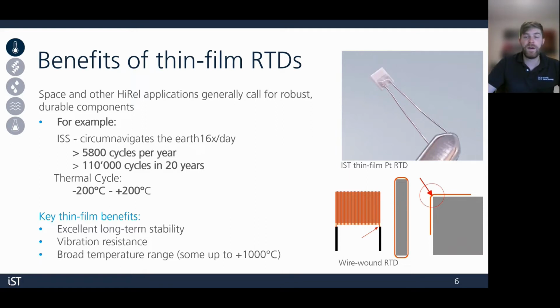On the bottom right, we have an example of a traditional wire wound RTD. These feature a very thin wire wrapped around a cylindrical or rectangular substrate. These wires can become damaged with vibration and repeated thermal cycles, especially when we're working with high resistance RTDs since the wire would be extra thin. At the top right, we have a thin film platinum RTD. The one pictured here is one of the ESCC qualified elements. With these, the platinum is physically bonded to the substrate with the sputtering process, so there's less of a concern for damage from thermal cycling or vibration.